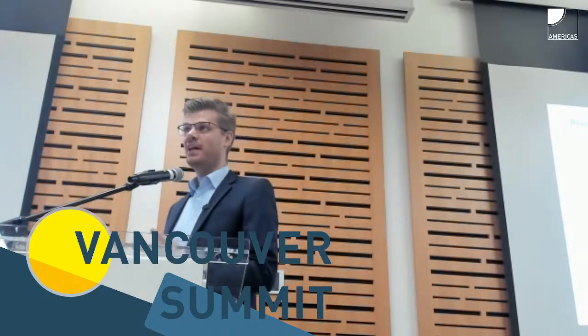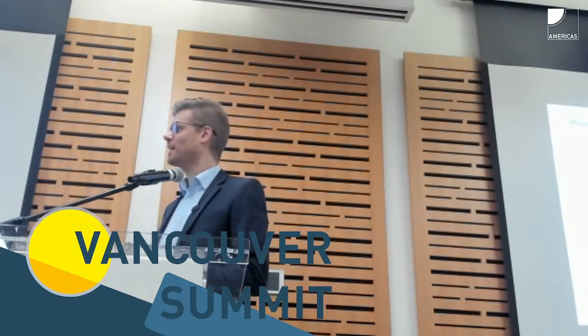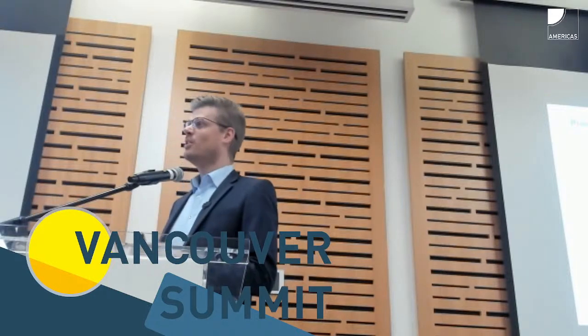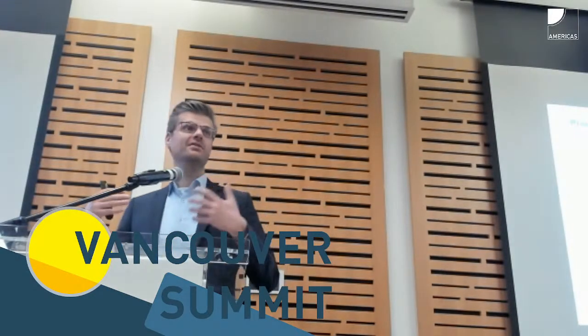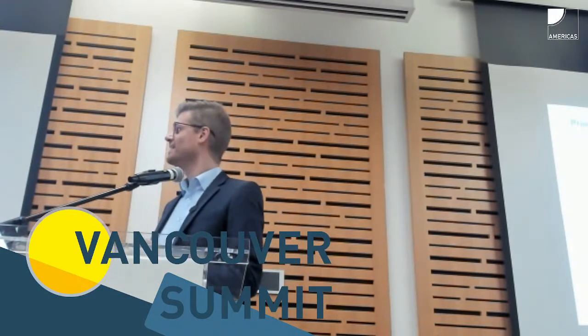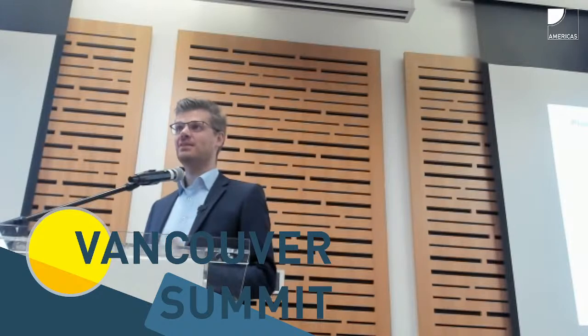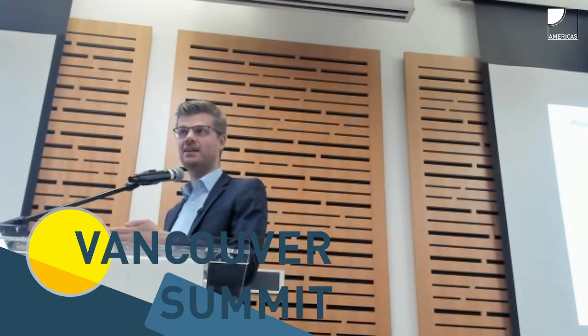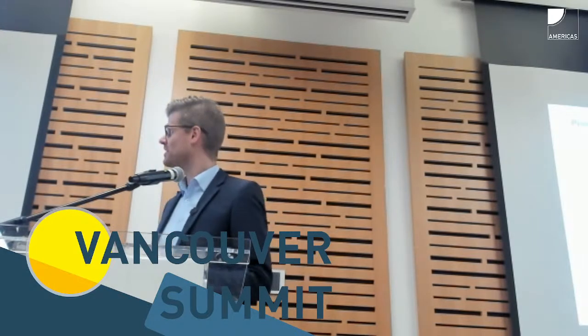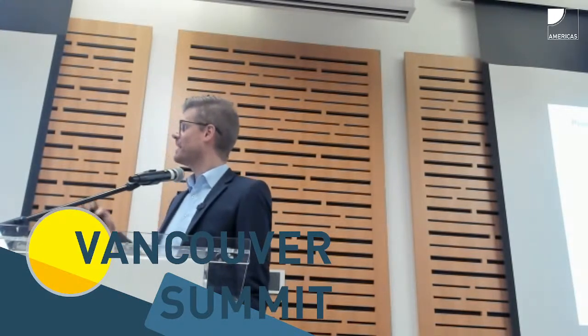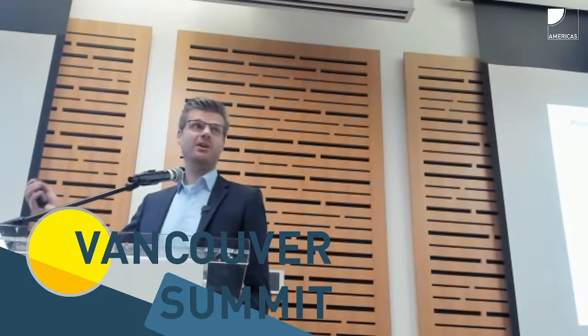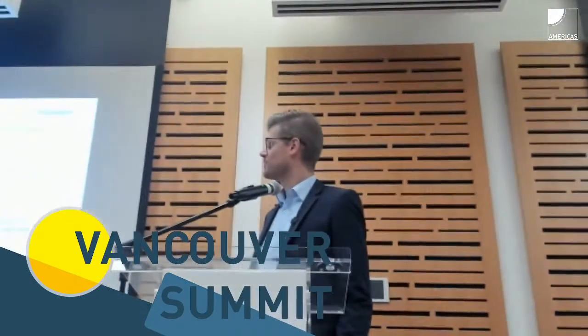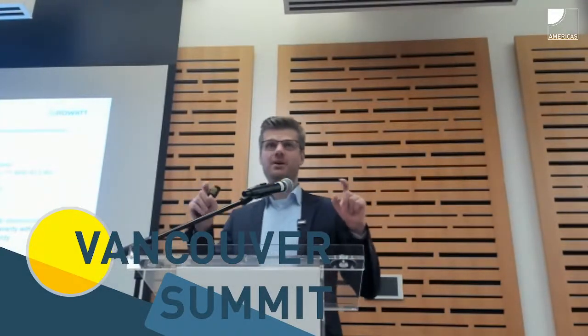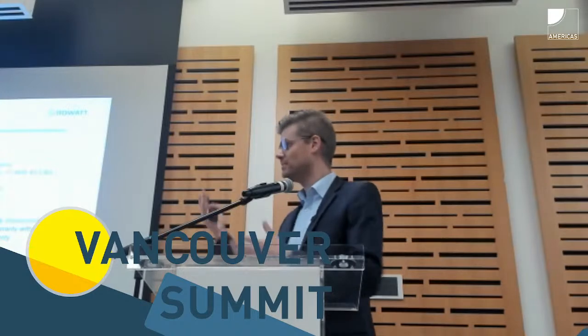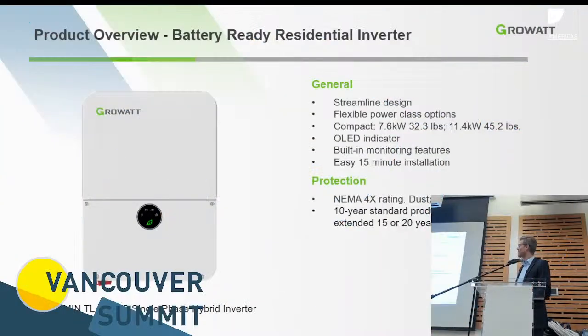The Growatt design is a multi-level switching topology, similar to what SolarEdge, for example, had and SMA has in a few products, which is significantly more efficient. Therefore, the power loss that goes into heat is smaller, and therefore they can use a plastic housing with an aluminum heatsink in the back that is actually quite small because the efficiency is pretty good. This makes the inverter very, very light, very easy to install because it's just 32 pounds for the smaller ones and 45 pounds. So with that bracket you mount to your studs or to the back plate, drywall or plywood piece, it's very easy to hang the unit.